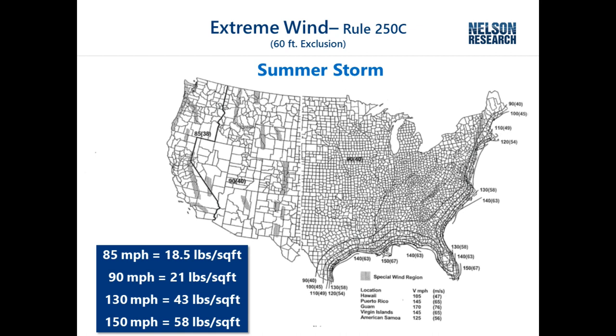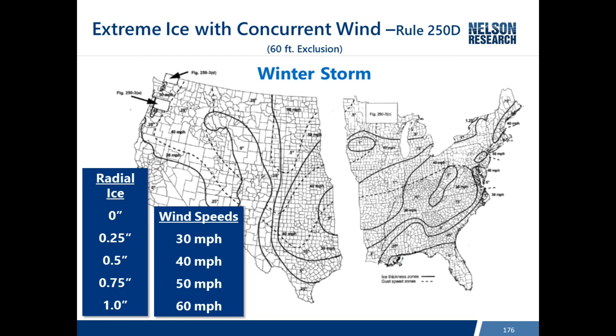Rule 250C represents an expected summer storm and has a 60-foot exclusion — it only applies to poles extending more than 60 feet above ground. Along coastal areas, wind speeds and pressures increase significantly; 90 mph equals 21 pounds per square foot, and 130 mph equals 43 pounds per square foot. Rule 250C addresses summer storms without ice. Rule 250D represents a winter storm with extreme ice — radial ice ranging from zero to one inch — and whatever concurrent wind speed was recorded, from 30 to 60 mph.